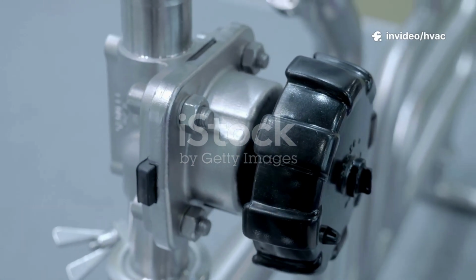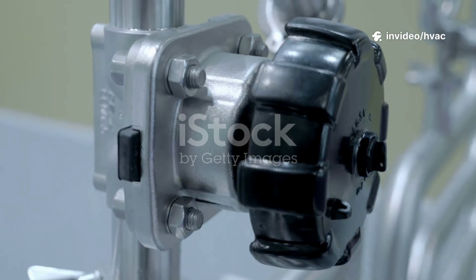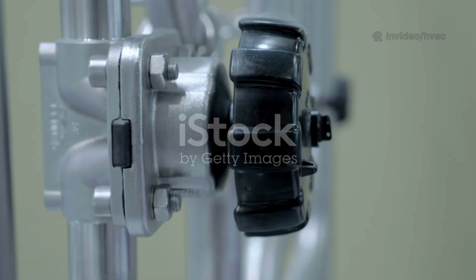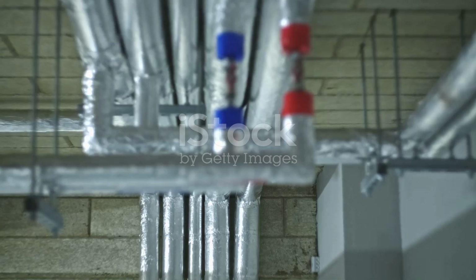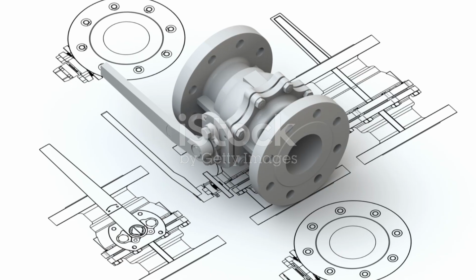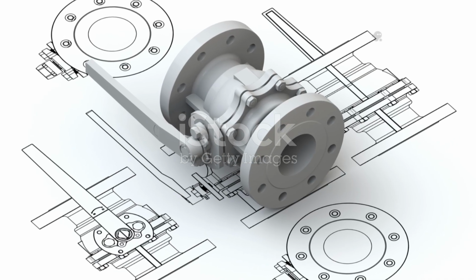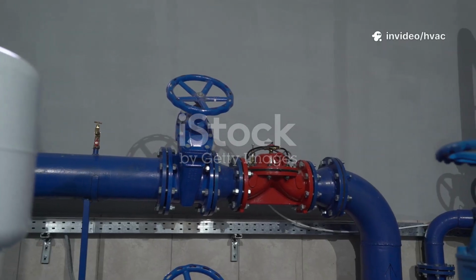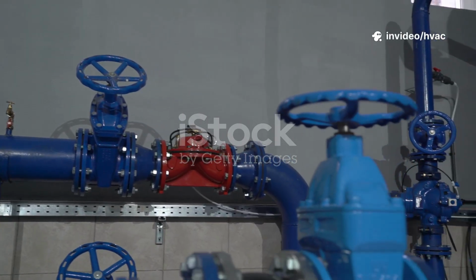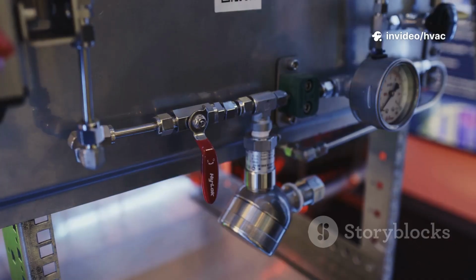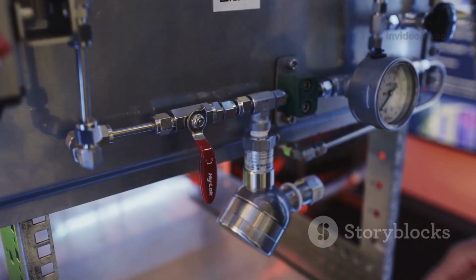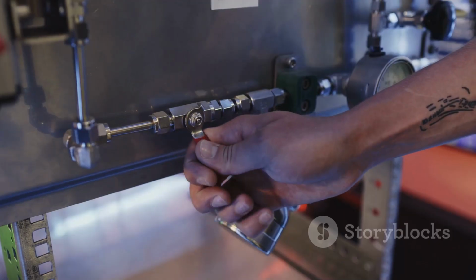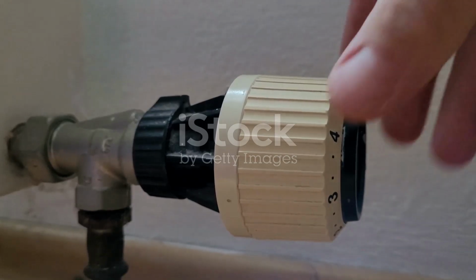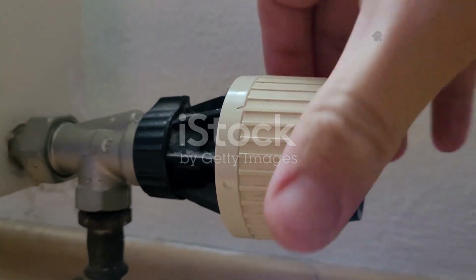A pressure-independent control valve, often called a PICV, is a special type of valve used in modern heating and cooling systems. It's not just one simple valve. Think of it as three important parts combined into a single compact body. The first part is an automatic balancing valve, which helps control the water pressure. The second part is a differential pressure regulator, a key component that makes it pressure independent. The third part is a standard two-way control valve, which adjusts the flow of water.